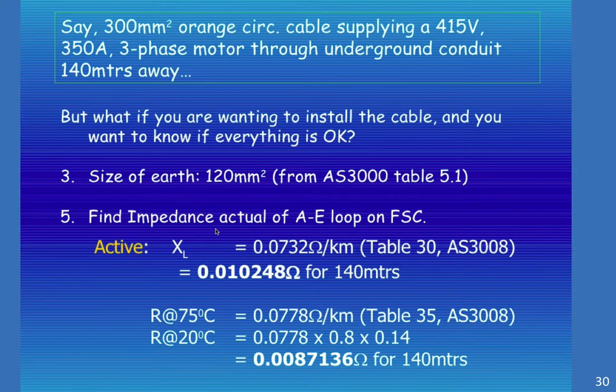Find the impedance of the actual earth loop on FSC. The active XL is 0.0732Ω/km from table 30, AS3008, which is 0.010248Ω for 140 meters. Assuming 75°C worst case, from AS3008 table 35, the resistance R is 0.0778Ω/km or 0.0778 × 0.8 × 0.14 = 0.0087136Ω for 140 meters. So we now have XL and R.